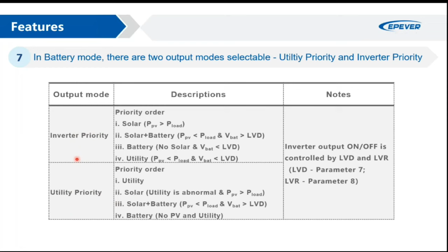If you remember, we had a switchover circuit. This switchover circuit had to switch the AC output between the inverter and the utility. The transfer time is, in any case, smaller than 15 milliseconds.